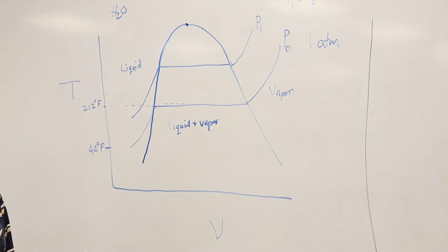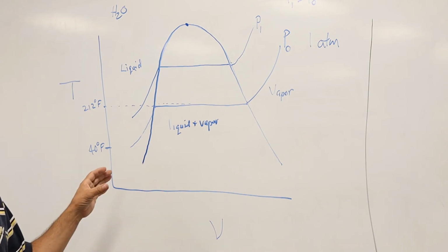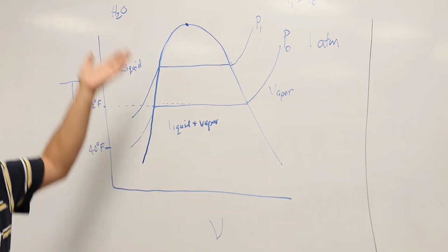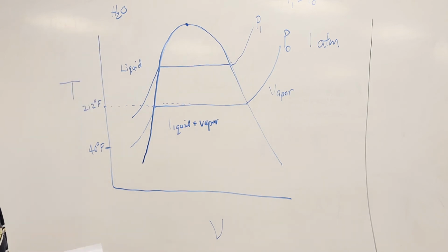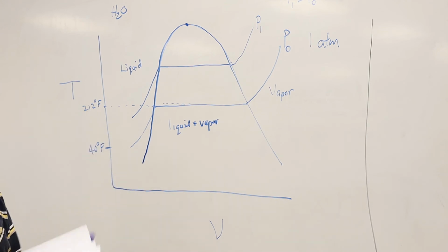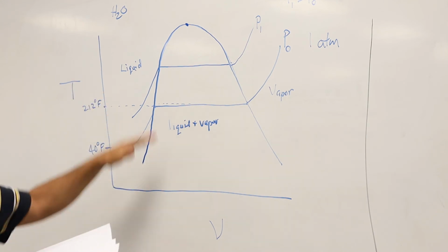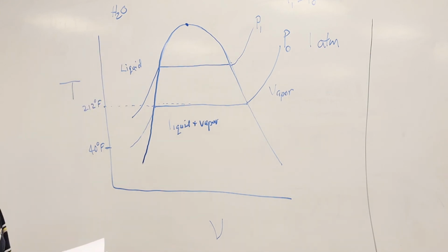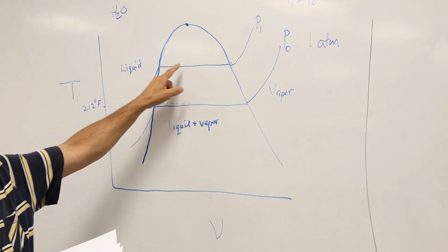That's right. Okay. And it's important in a boiling water reactor because the water is coming into the reactor to be warmed up, right? You have the reactor fissioning, creating heat. You want to make sure that the water coming into the reactor stays in the liquid state until you get up through a portion of the fuel assemblies themselves and have the boiling occur there. You don't want the water to start boiling soon after it gets in the reactor. You want it routed up into the fuel region before it hits this saturation point and starts turning into steam.